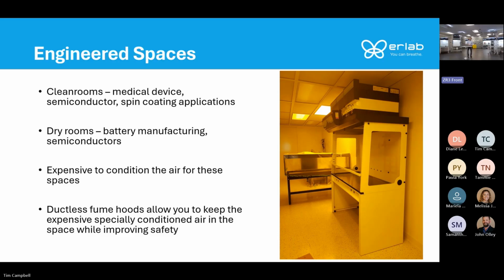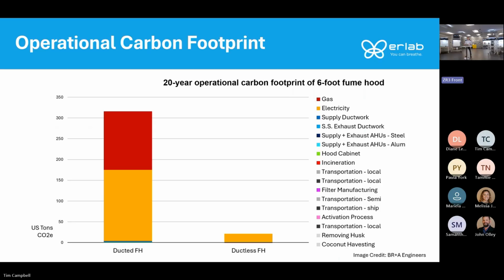That's going to then take all that dry conditioned air and blow it outside. There'll be more of that to make up. So especially in battery manufacturing, there's HEPA filtration for the powders as well as the carbon filtration for the liquid chemicals. So it's been a very big application. If you work in battery manufacturing and you don't have a hood, a ductless fume hood is an option for you. As I said, it's very expensive to condition that air to make it either super clean or super dry. Which then leads me to comparing the operational carbon footprint of a ducted fume hood versus a ductless fume hood.